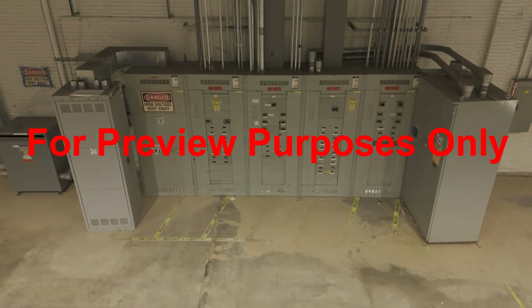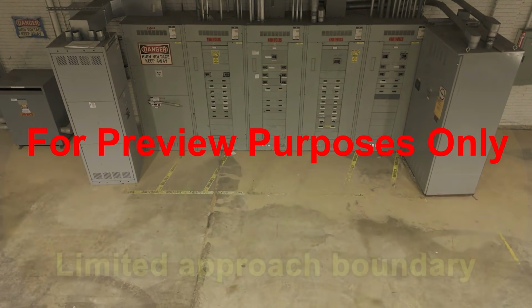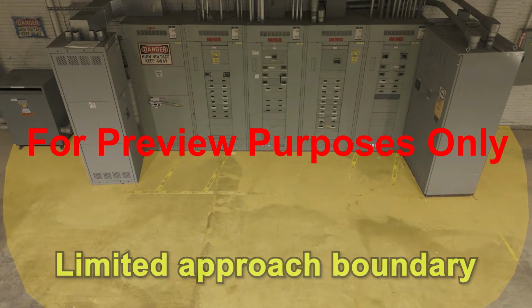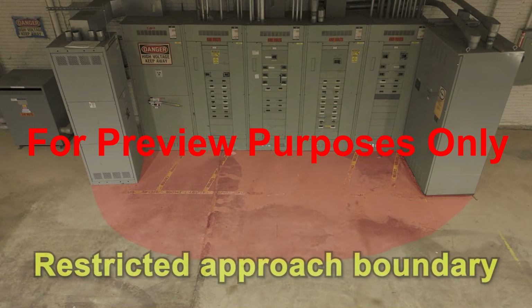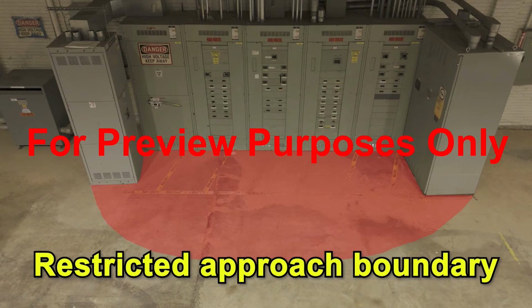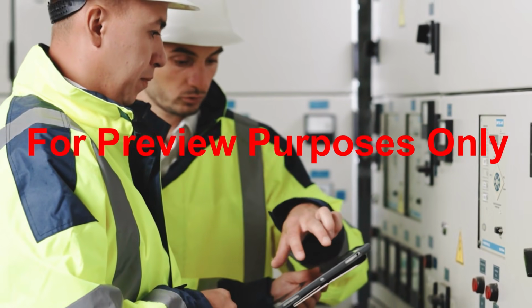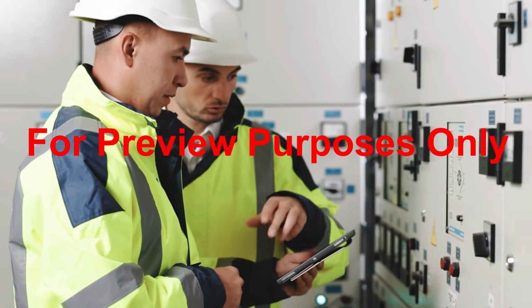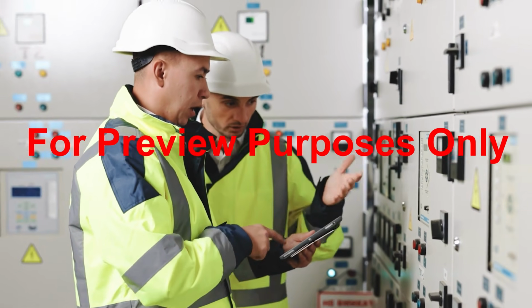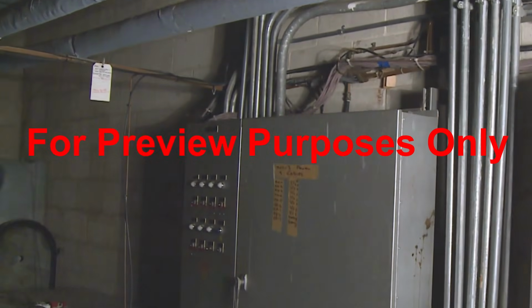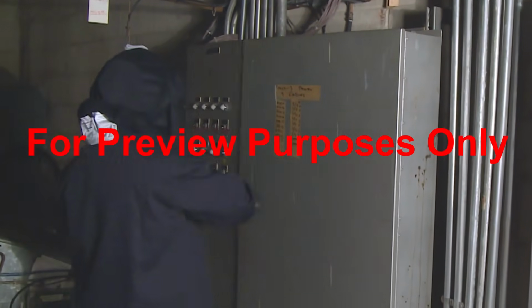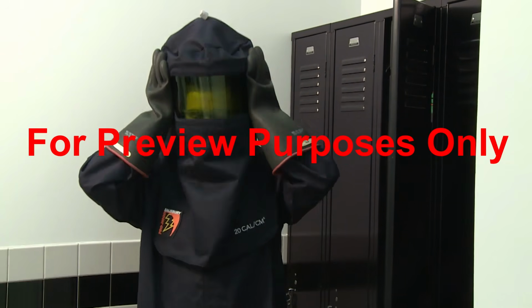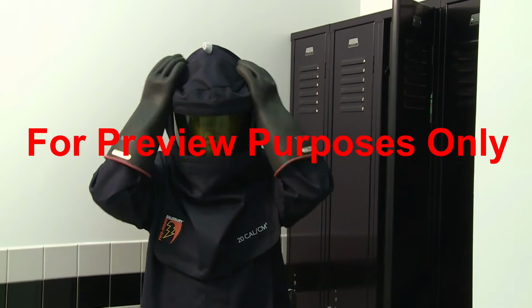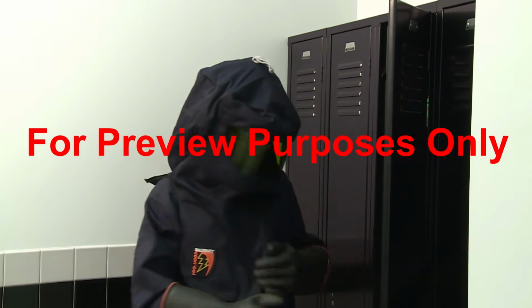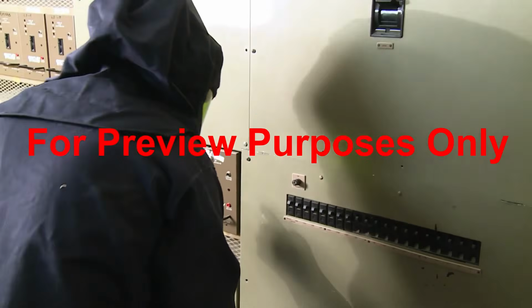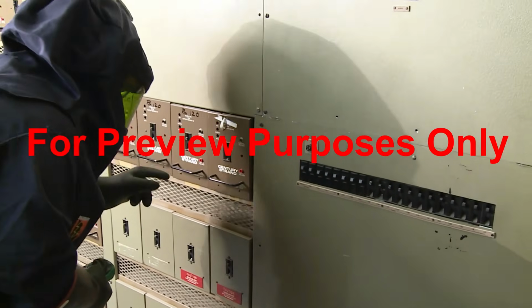The main difference is that the area within a limited approach boundary poses less of an electrical risk than the area within a restricted approach boundary. So while unqualified personnel can enter the limited approach boundary with a qualified chaperone, only qualified personnel are allowed to enter a restricted approach boundary. And specialized PPE that isn't needed in a limited approach boundary may be required in a restricted approach boundary.